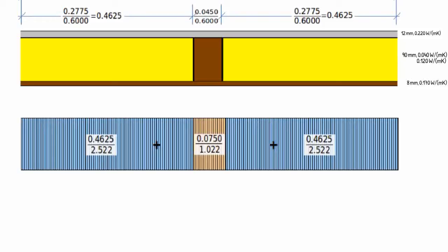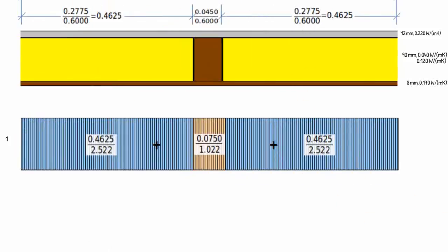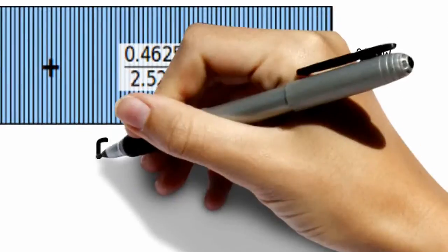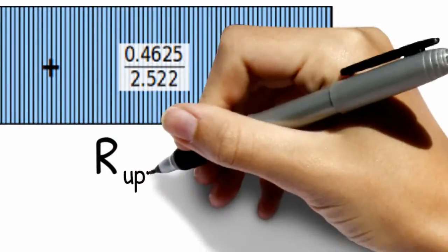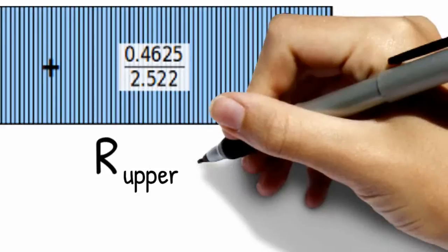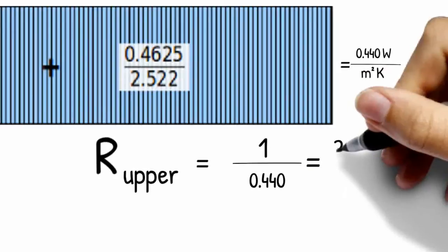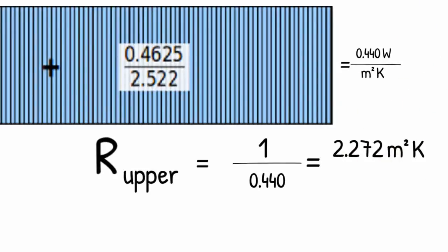Now we start with area weighting and taking the percentage of the ranges and putting this over the resistance of that range. By doing this we get the inverse of the upper margin of our thermal resistance range. Inversing this again gives us our upper margin of the thermal resistance range. In our case, 2.272 square meter times kelvin over watt.